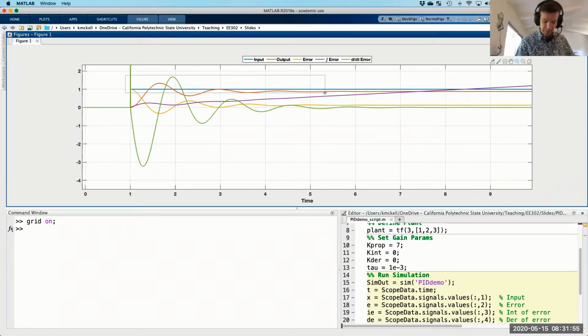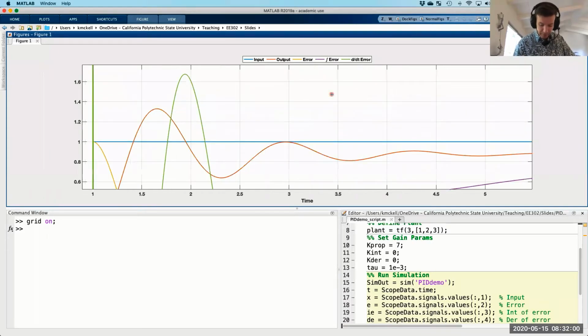Yeah, that might work. Okay, here we go. So it looks like the steady state value of this curve is a little under 0.9. So I'm calling this a little over 0.1 of an amplitude. And then this goes from here, there's a 0.1, there's a 0.2, there's another 0.1. So this is a little bit more than quarter amplitude decay, because this peak is now about 0.5 in height, and this peak is only about 0.1 in height relative to this imaginary steady state line going through the 0.9 line. You follow that?